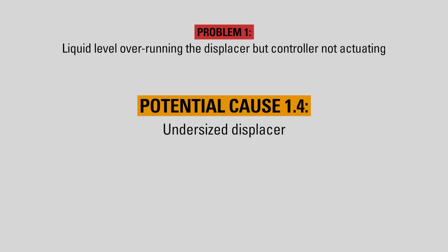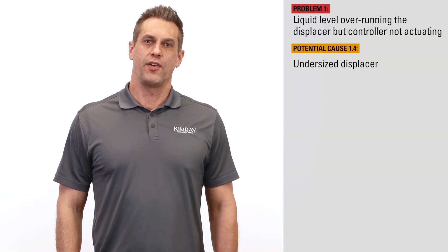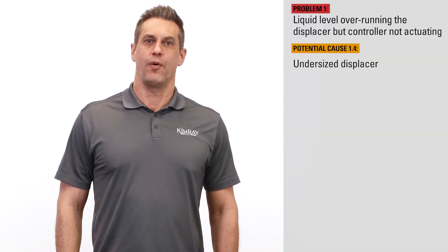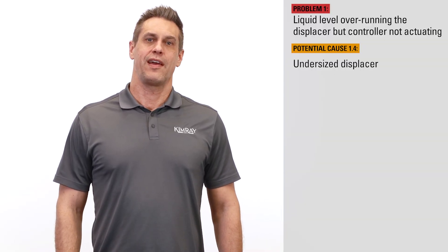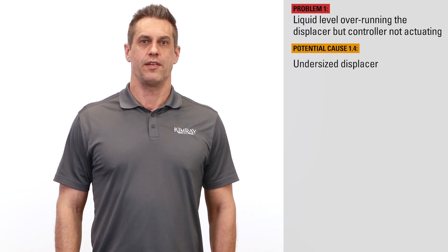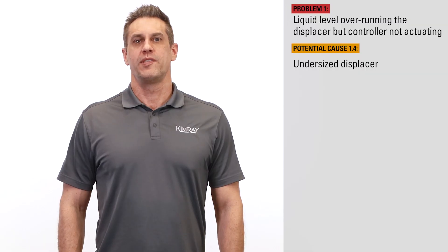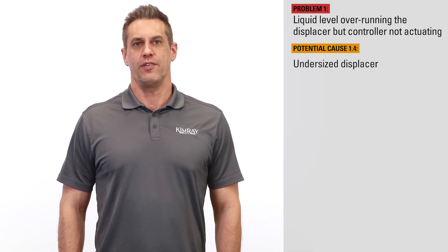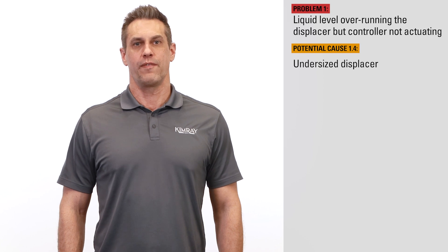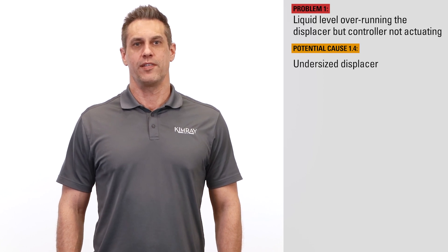If by adjusting the spring tension and span settings you're still not able to alleviate the problem at both ends, this could be an indication that the displacer is undersized. When interfacing, if the specific gravity differential is below 0.2, buoyant force from the displacer may not be sufficient to actuate the controller. A larger Kimray displacer may be necessary. Over time, specific gravities in your system can change, which can account for a controller that was working fine but then started having these issues.